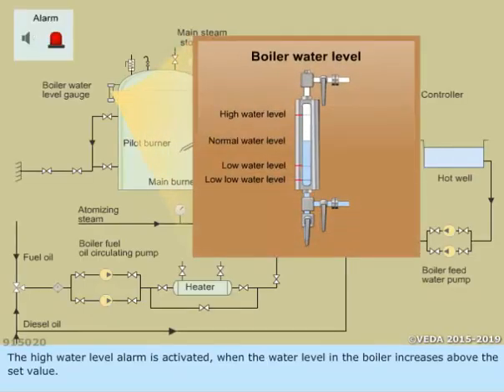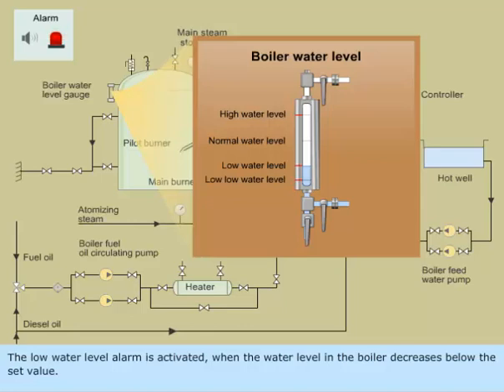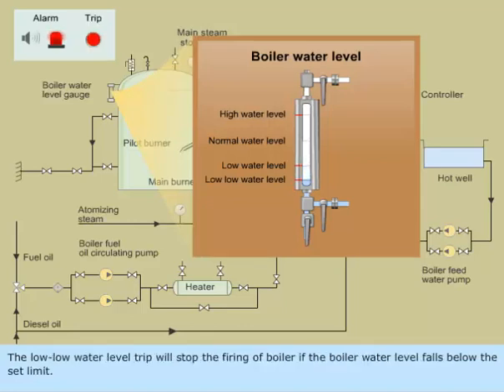The High Water Level Alarm is activated when the water level in the boiler increases above the set value. The Low Water Level Alarm is activated when the water level in the boiler decreases below the set value. The Low Low Water Level Trip will stop the firing of the boiler if the boiler water level falls below the set limit.